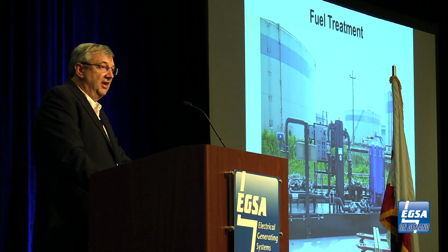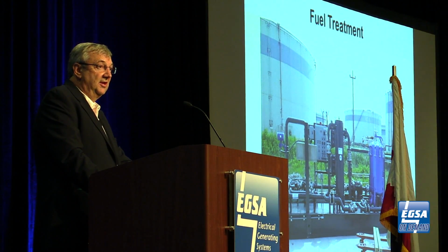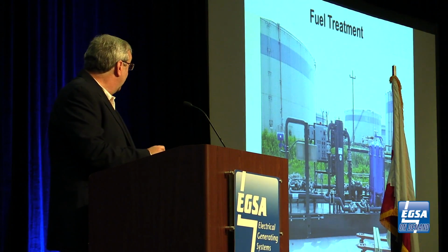Fuel treatment, having the right assets, correct filtration. It's a lot easier to do redundant fuel systems and address fuel at 150 liters a minute, instead of going down to the engine and having to change Racors on 100 engines and change the primary filters on the engines as well. Address it up front. As the fuel's coming off the trucks, aggressively treat that fuel, pull the water out of it, pull all the contaminants out of it, and make our lives easier for preventive maintenance on the power plant.